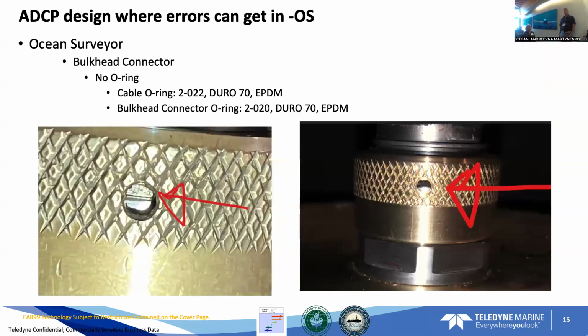Other problem is the O-rings for the bulkhead connector. You can see here, there's no O-ring, and then you can see it right here. There's a little black O-ring that's seated. There's actually 2. There's a second O-ring inside the bulkhead connector on this side. But that one usually doesn't fall out because you're not usually tipping over the transducer. But this cable one will fall out sometimes when you're putting it in and you're not paying attention. So that's why there's a sight hole, so you can always triple check you have an O-ring installed.